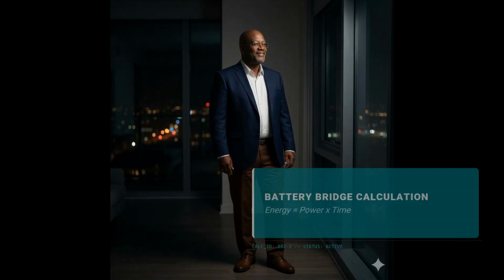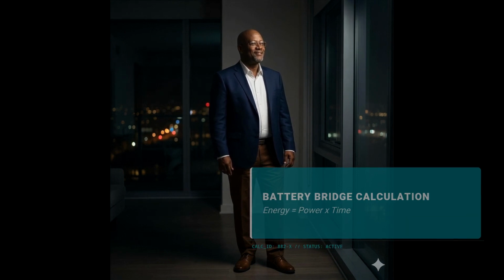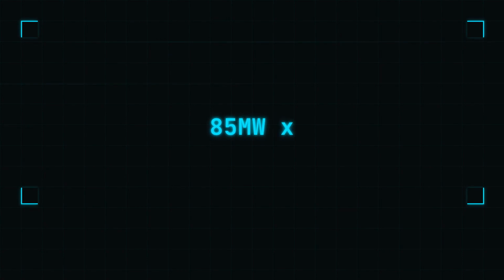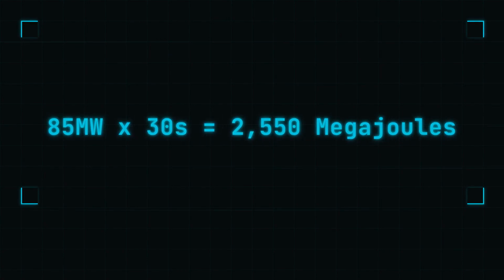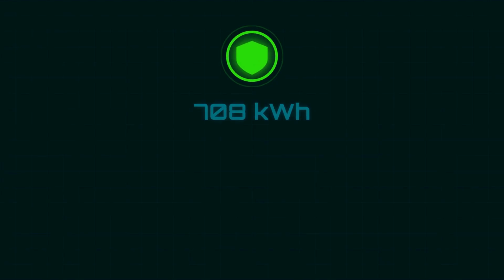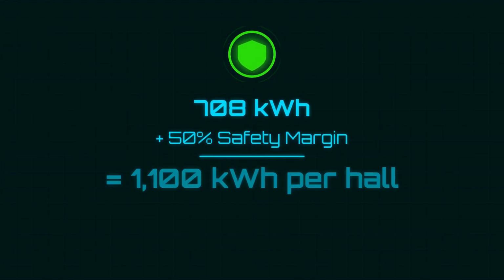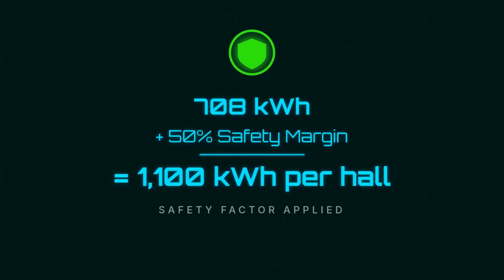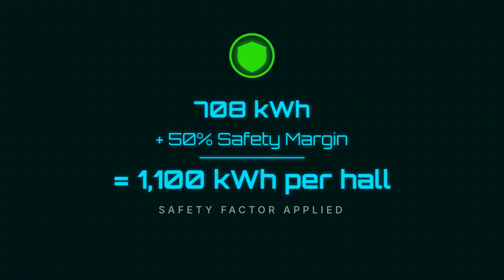Now for the critical engineering question, how much battery energy do we actually need to bridge 85 megawatts for 30 seconds? The math is straightforward, but the resulting numbers are staggering and require careful consideration. Energy required equals power multiplied by time. 85 megawatts multiplied by a 30-second generator start window gives us 2,550 megajoules. That is approximately 708 kilowatt hours of raw bridging energy needed at the bus. But we must account for battery aging and worst-case extended start scenarios. By adding a 50% safety margin, our design capacity becomes approximately 1,100 kilowatt hours per data hall group to ensure reliability throughout the life cycle. That results in 4,400 kilowatt hours across the entire campus.